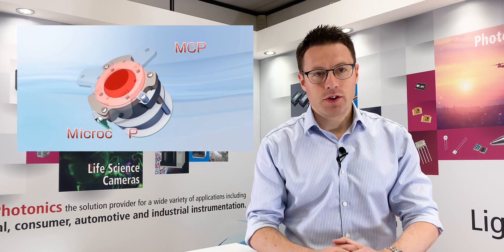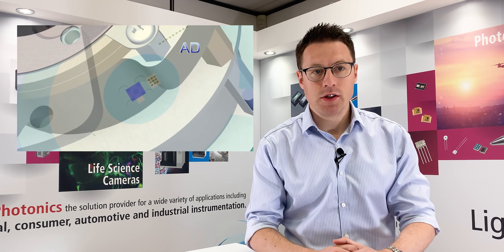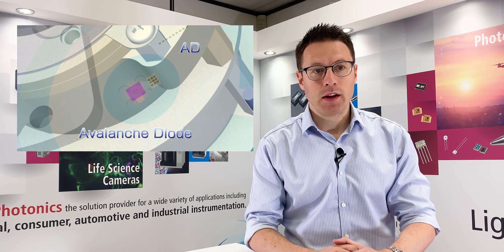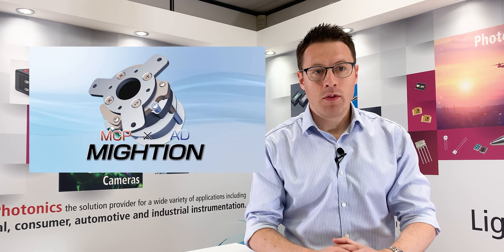Can you show us in more detail how this detector works? Sure. Here is the basic structure of the MIGHTION. The MCP sits at the front of the detector with the avalanche diode situated towards the rear. These elements are enclosed within a compact mechanical assembly. Ions entering the detector move towards the MCP and undergo ion-to-electron conversion.